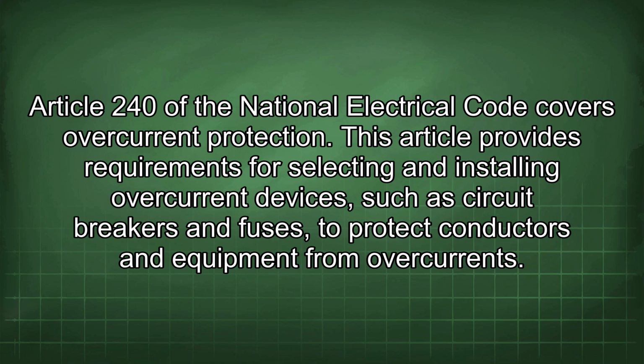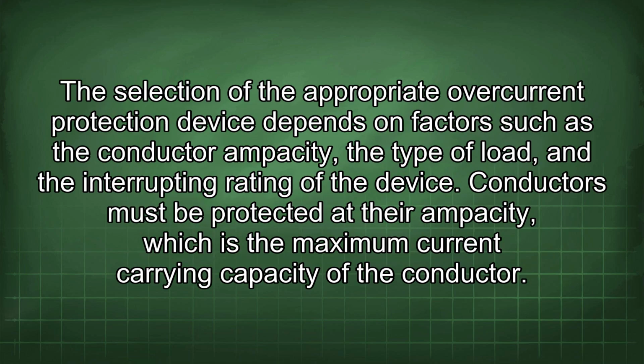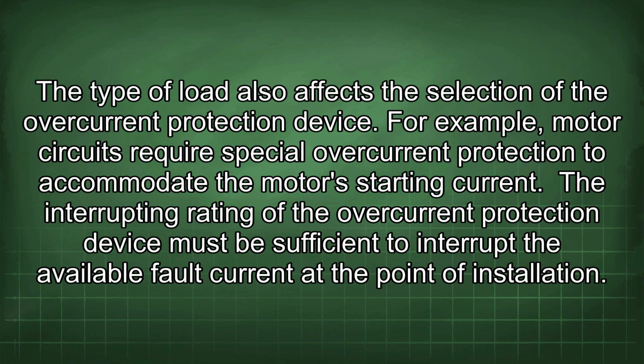This article provides requirements for selecting and installing overcurrent devices, such as circuit breakers and fuses, to protect conductors and equipment from overcurrents. The selection of the appropriate overcurrent protection device depends on factors such as the conductor ampacity, the type of load, and the interrupting rating of the device. Conductors must be protected at their ampacity, which is the maximum current carrying capacity of the conductor.